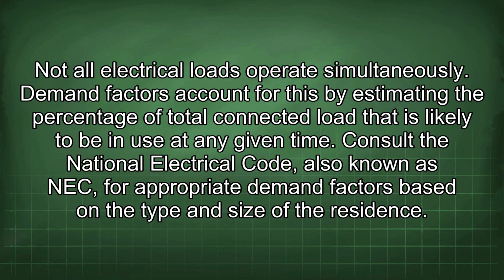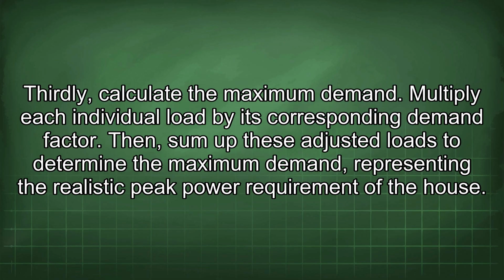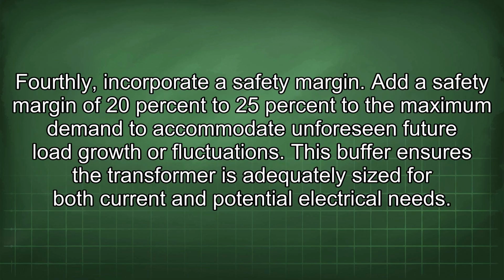Consult the National Electrical Code, also known as NEC, for appropriate demand factors based on the type and size of the residence. Thirdly, calculate the maximum demand. Multiply each individual load by its corresponding demand factor. Then, sum up these adjusted loads to determine the maximum demand, representing the realistic peak power requirement of the house. Fourthly, incorporate a safety margin. Add a safety margin of 20% to 25% to the maximum demand to accommodate unforeseen future load growth or fluctuations. This buffer ensures the transformer is adequately sized for both current and potential electrical needs.